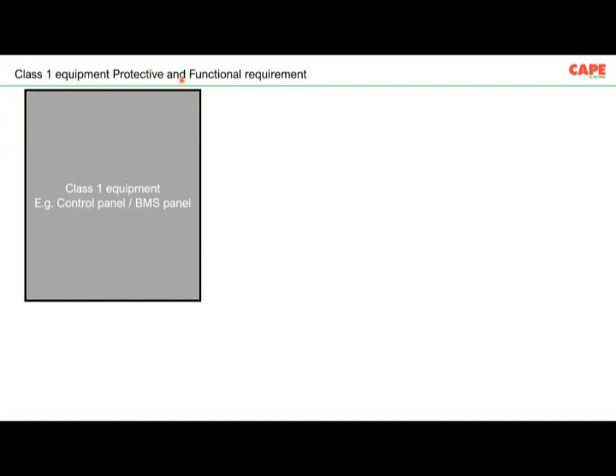Class 1 equipment: what is protective and functional earthing? Now, imagine you have a panel board. The panel board will have three-phase, neutral, and the PE terminal. PE terminal means the protective earth terminal. In order to achieve safety, you are supposed to connect it to somewhere.